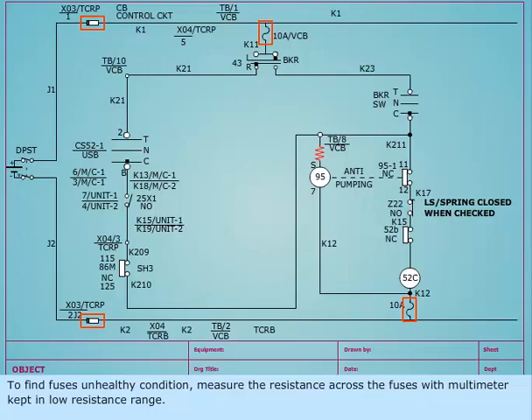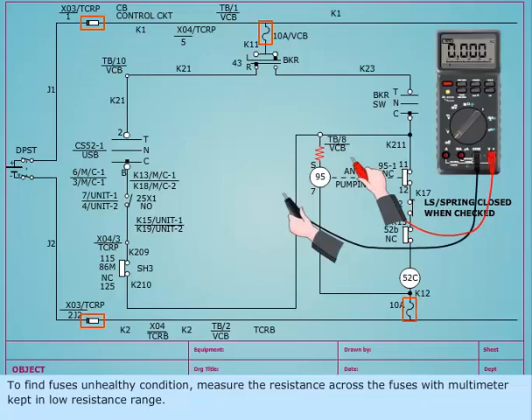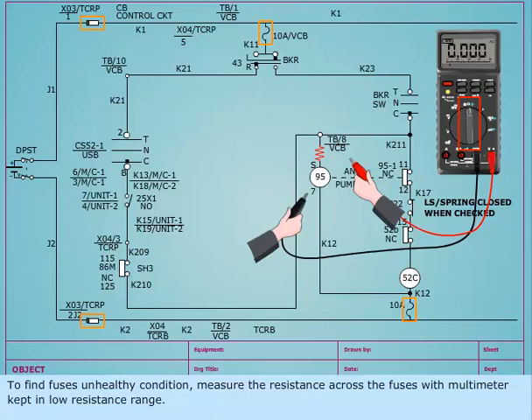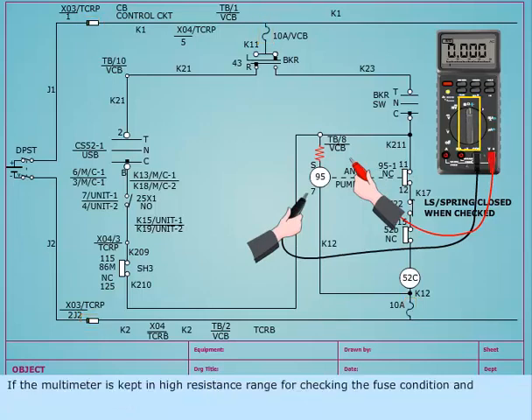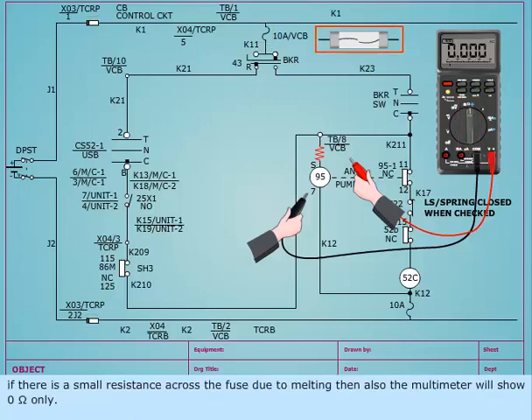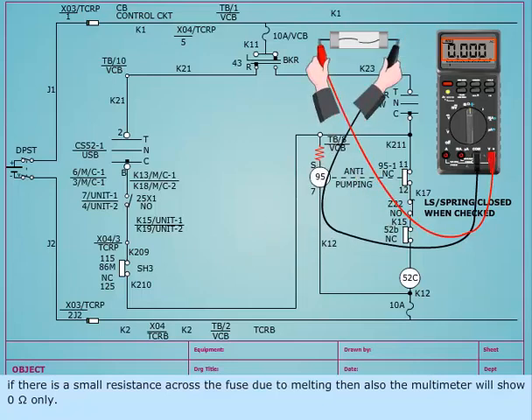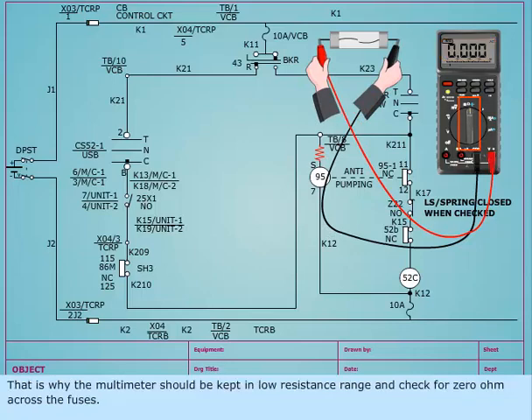To find fuses in an unhealthy condition, measure the resistance across the fuses with the multimeter kept in low resistance range. If the multimeter is kept in high resistance range for checking the fuse condition and there is small resistance across the fuse due to melting, the multimeter will still show 0 ohm only. That is why the multimeter should be kept in low resistance range to check for 0 ohm across the fuses.